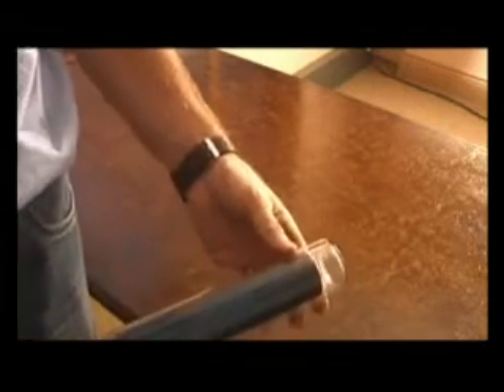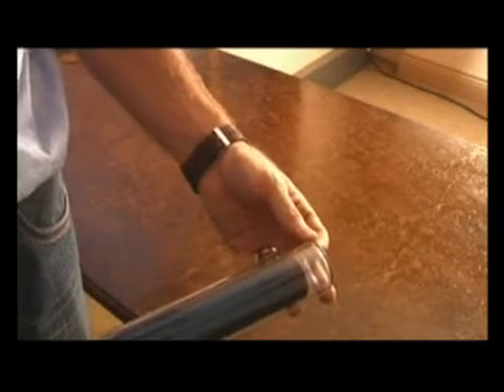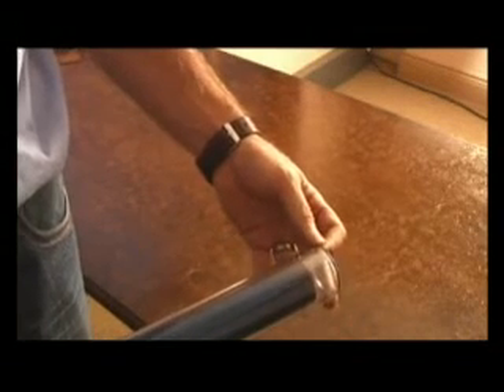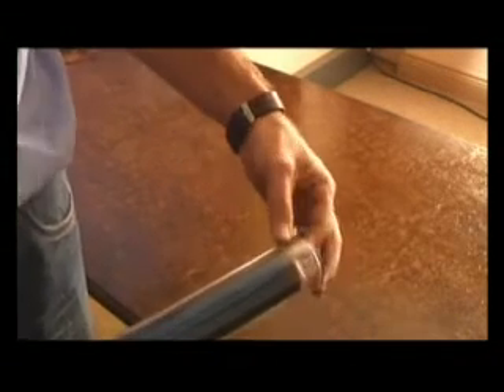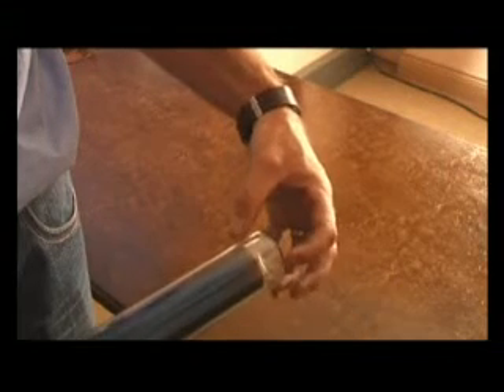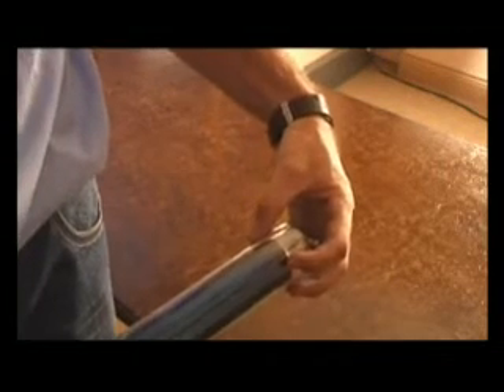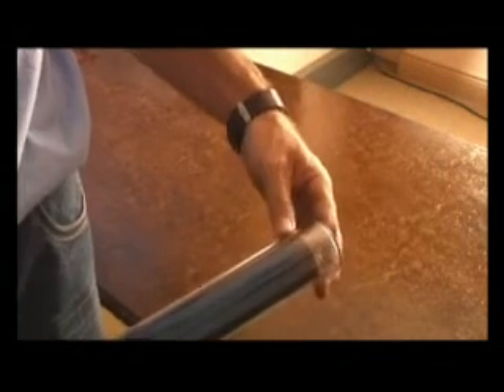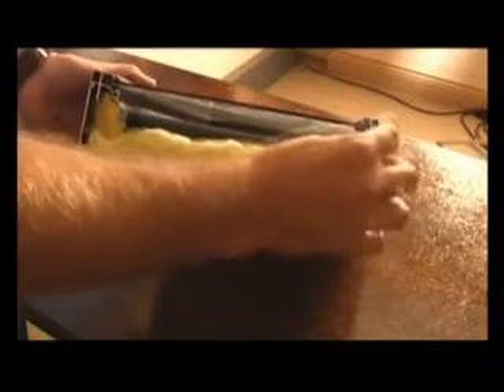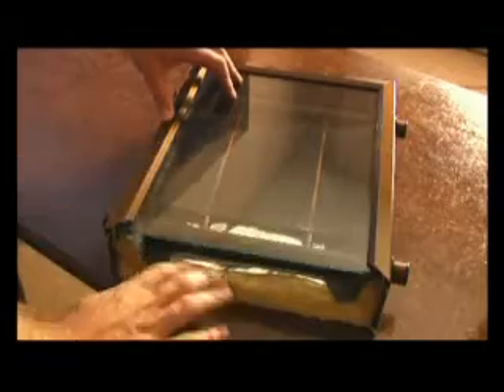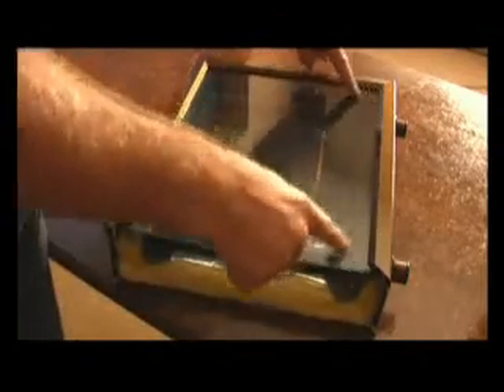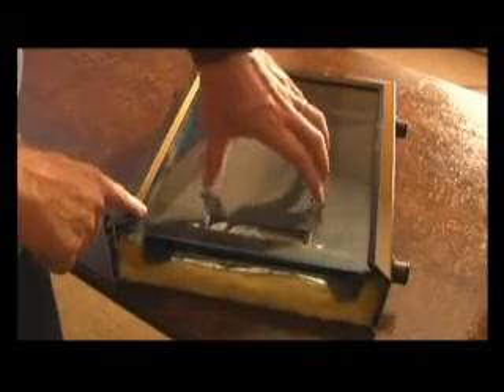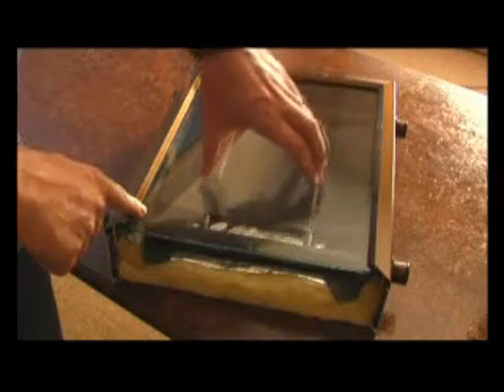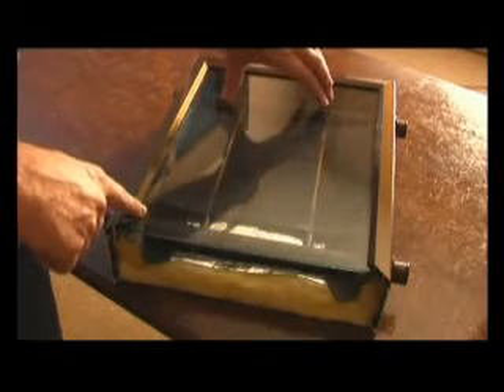Another form of evacuated tube system would be a low pressure system, or an instantaneous type system where the tube plugs into the tank directly and the water actually flows into the tube itself from the tank. On a flat plate panel we have an extruded aluminium casing. The glass covers an absorber plate connected to risers and two headers. The amount of risers depends on the size of the panel, and the size of the panel depends on the amount of water being heated.